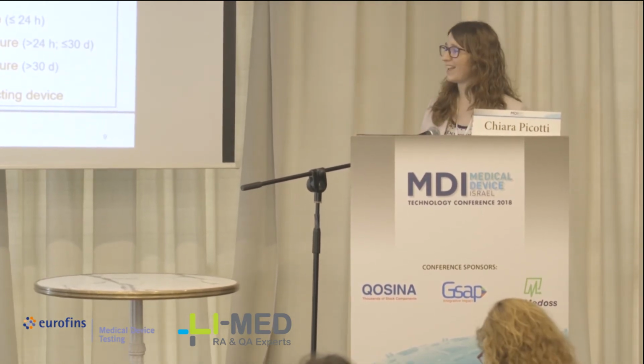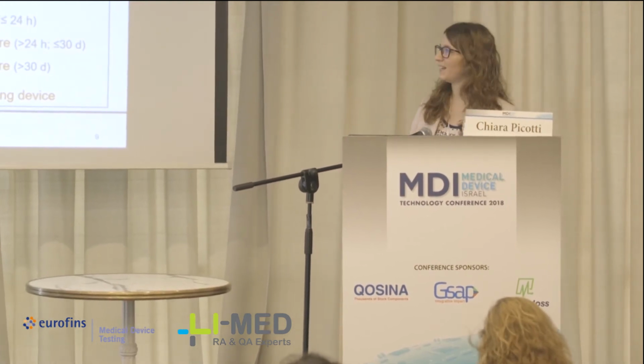But now the committee draft included another category of medical devices after providing us information about the categorization by the nature of contact and the time of contact. It is composed of the transitory contacting device. So all devices that have a really brief and transient contact with the human body, and for which basically biocompatibility is not necessary, except for some cases in which, even if the medical device has a really brief contact with the human body, some compounds, a component of this device can remain in contact with the body, like for example coatings or lubricants. In this case, even if the contact of the whole medical device is really short, we need to evaluate the biocompatibility.